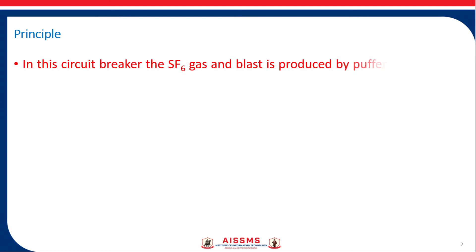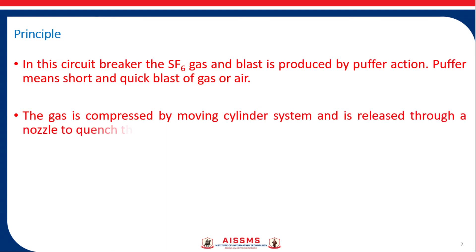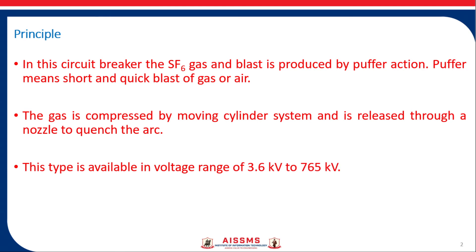Now let us see the working principle of the single pressure puffer type SF6 circuit breaker. In this circuit breaker, the SF6 gas blast is produced by puffer action — a short and quick blast of gas. The gas is compressed by a moving cylinder system and released through a nozzle to quench the arc. This type is available in a voltage range of 3.6 kV to 765 kV.